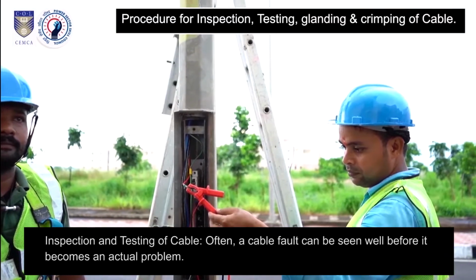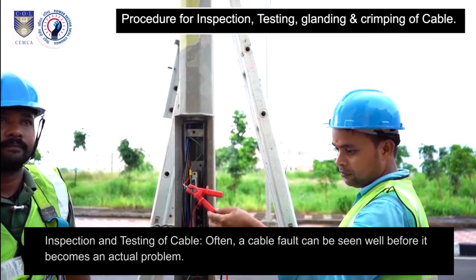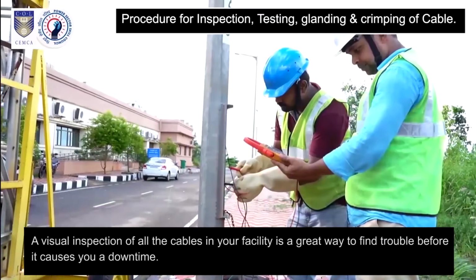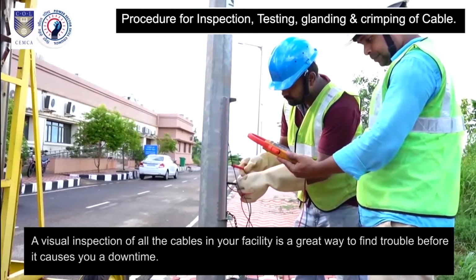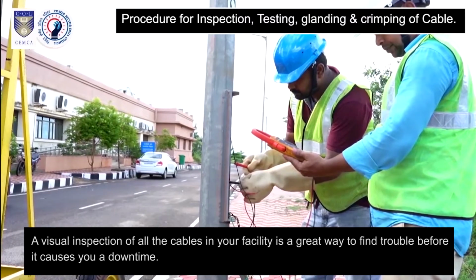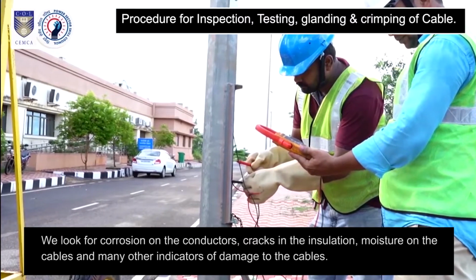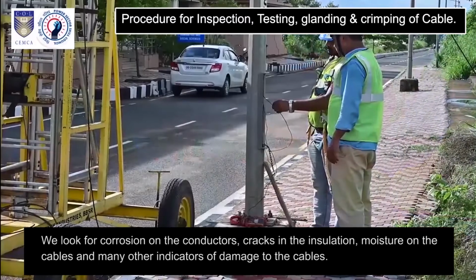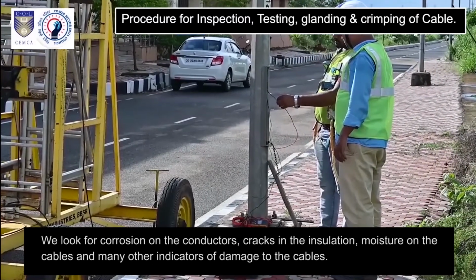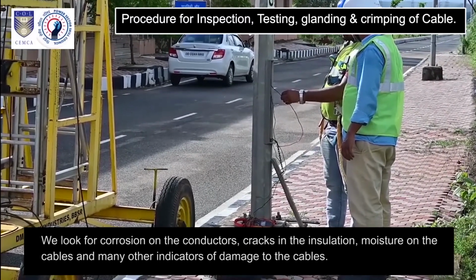Inspection and testing of cable. Often a cable fault can be seen well before it becomes an actual problem. A visual inspection of all the cables in your facility is a great way to find trouble before it causes you downtime. We look for corrosion on the conductors, cracks in the insulation, moisture on the cables and many other indicators of damage to the cables.